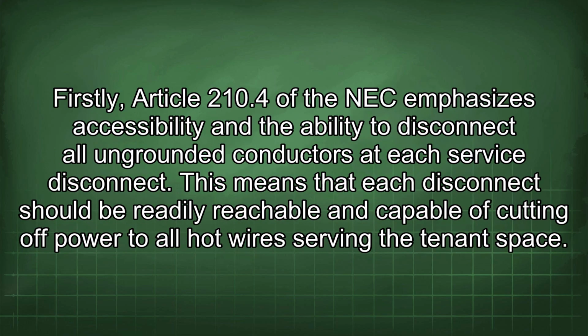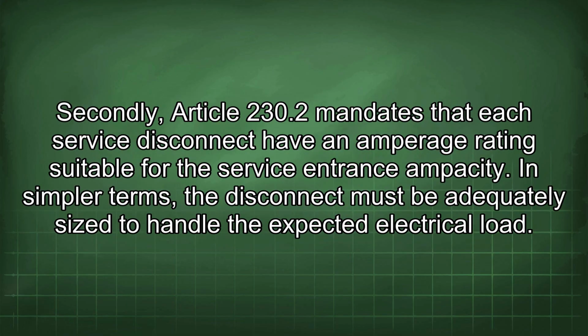Firstly, Article 210.4 of the NEC emphasizes accessibility and the ability to disconnect all ungrounded conductors at each service disconnect. This means that each disconnect should be readily reachable and capable of cutting off power to all hot wires serving the tenant space. Secondly, Article 230.2 mandates that each service disconnect have an amperage rating suitable for the service entrance ampacity. In simpler terms, the disconnect must be adequately sized to handle the expected electrical load.